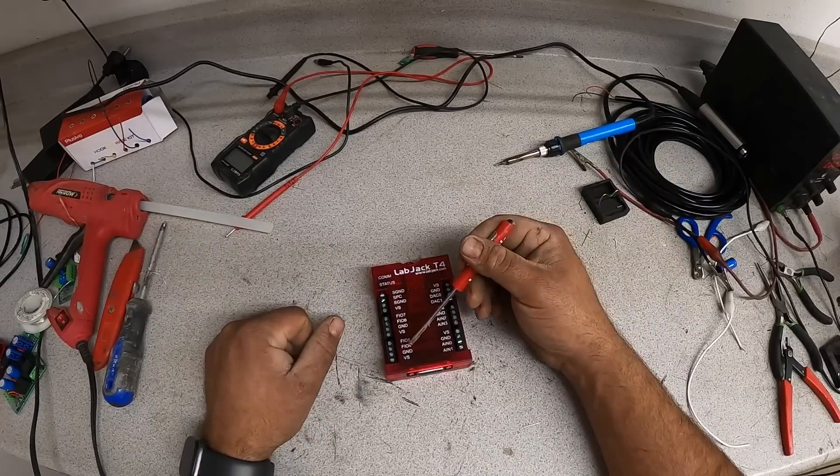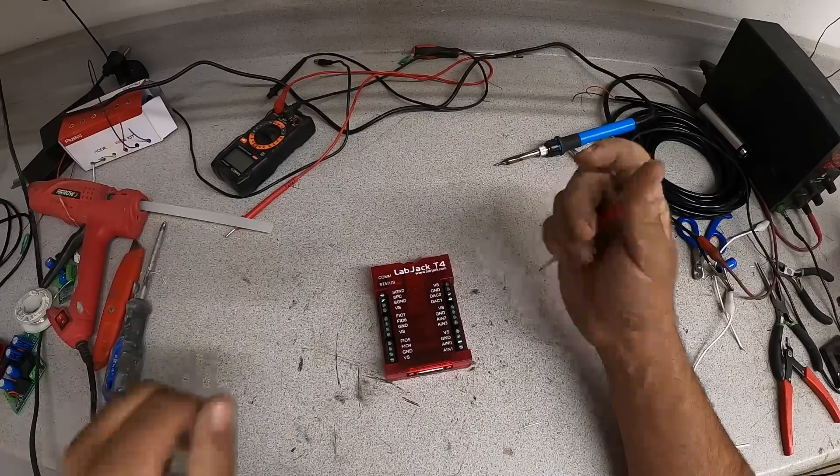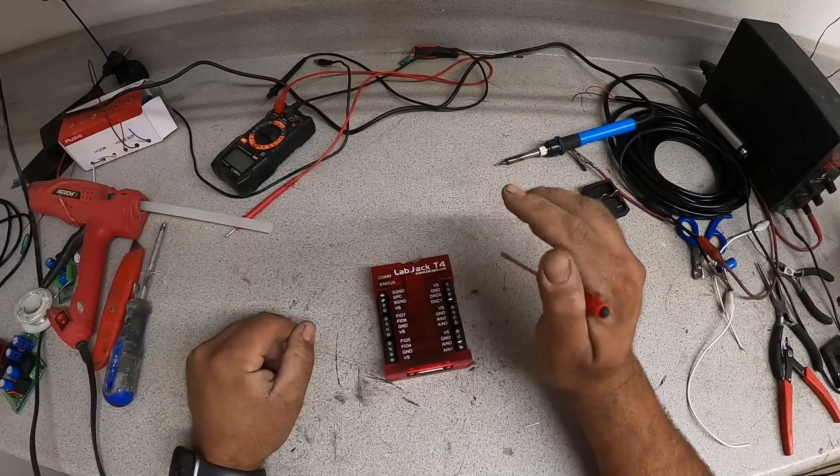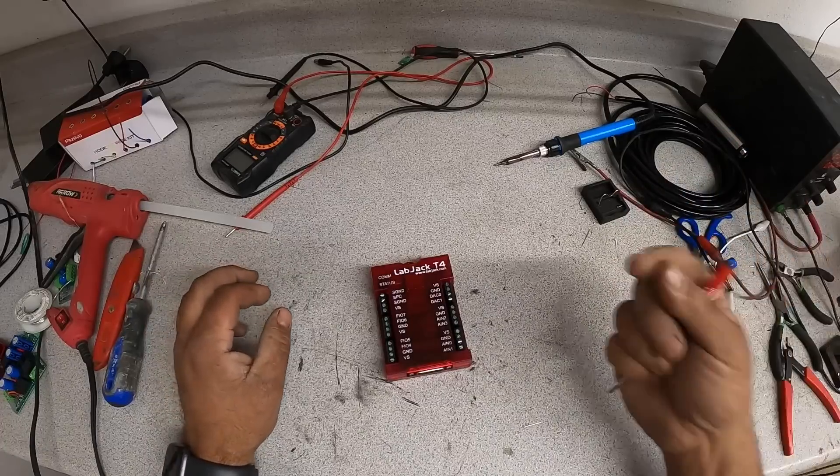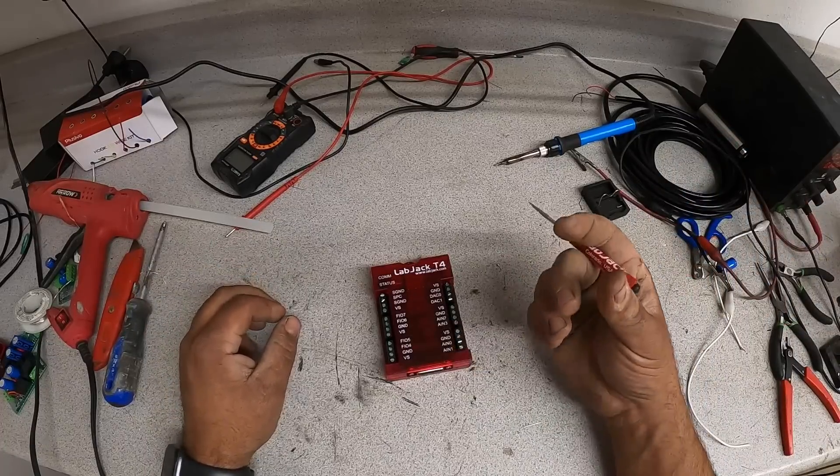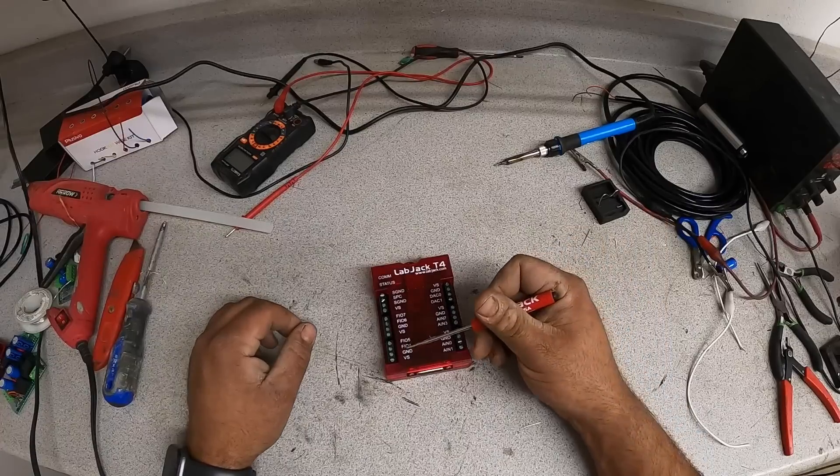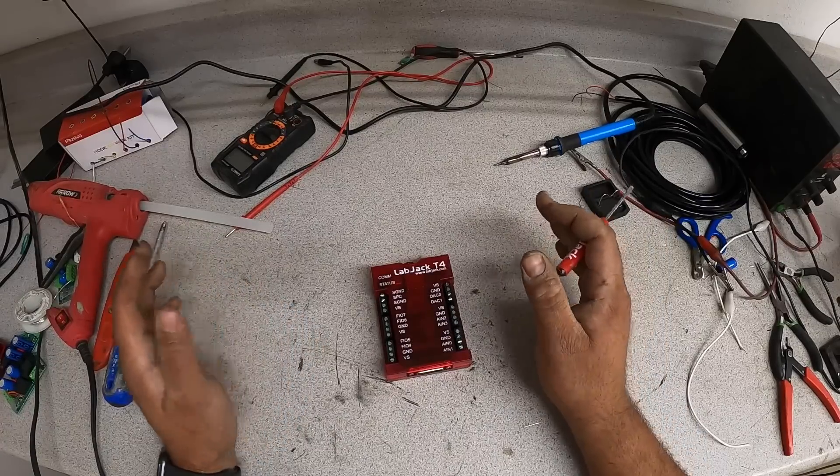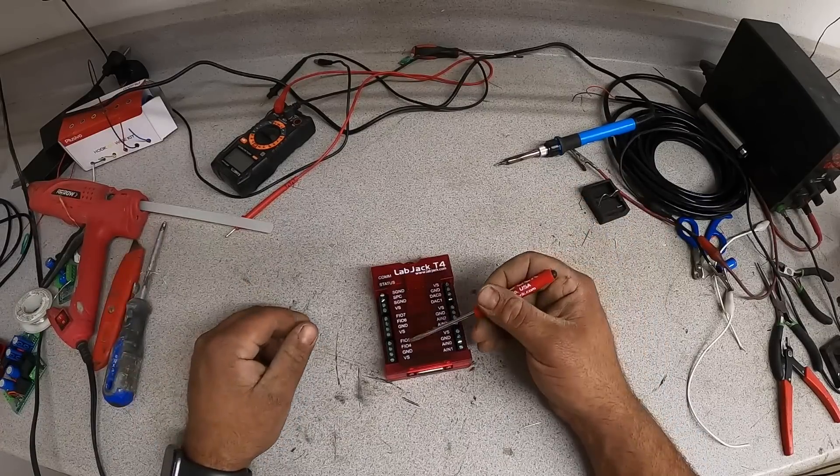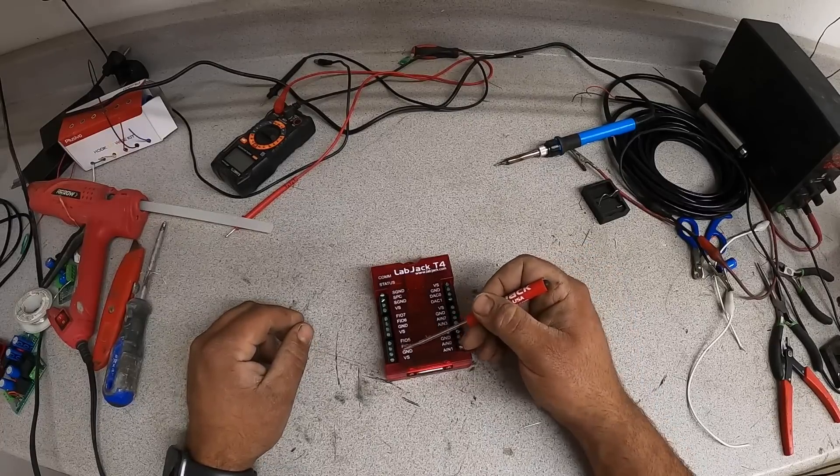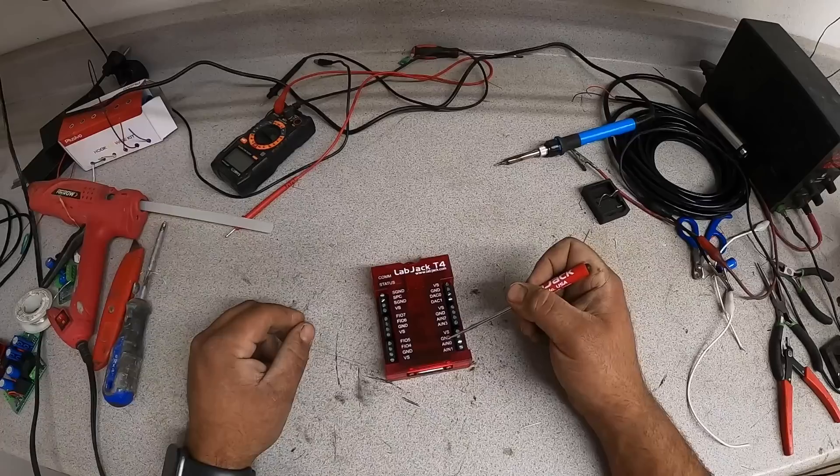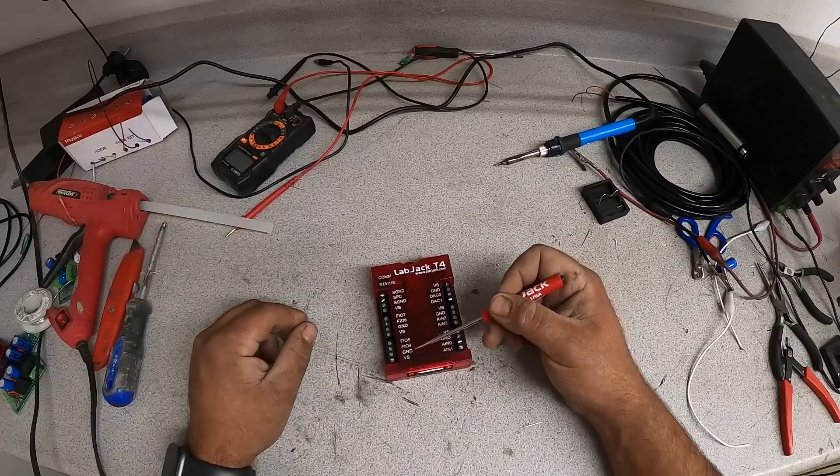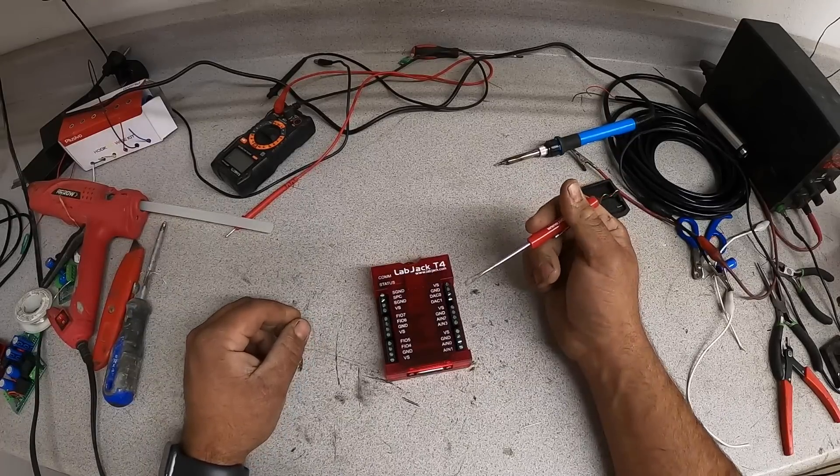you can use them as a digital input. If you've got something like a float switch or something when a level gets so high or a temperature gets so hot, it opens or closes, these can read that. It can read that on and off. You can also set them up in the computer as an analog input. The only difference then in this being an analog input in one of these is that this has a voltage limitation of 2.5 volts, where this one's got 10 volts voltage limitation. I don't know what this crap is, and I don't care. I haven't needed it yet.